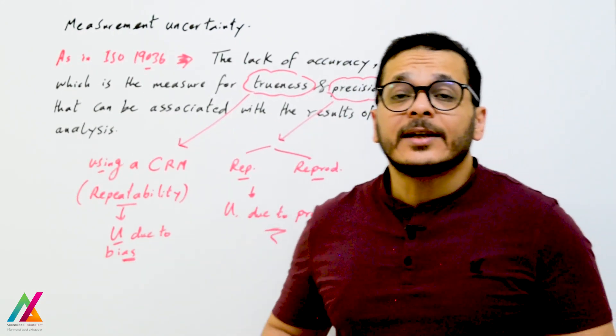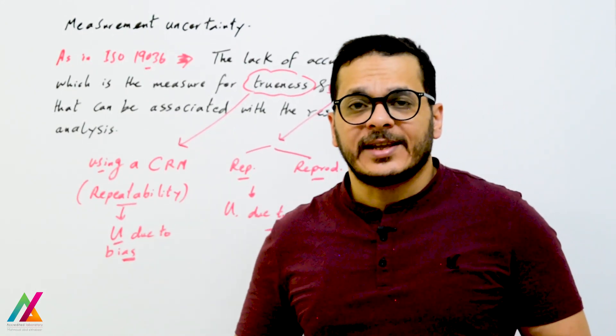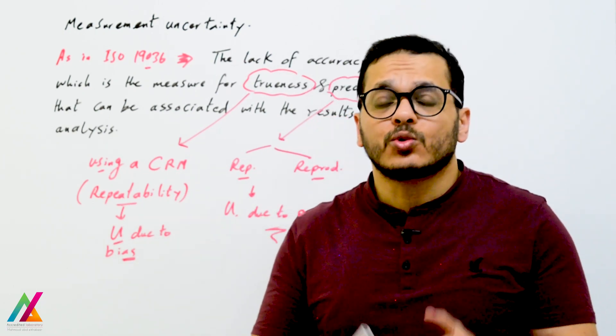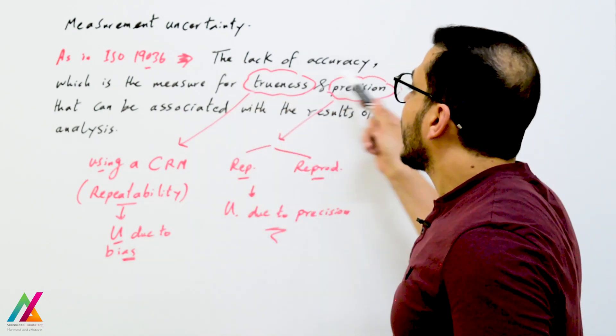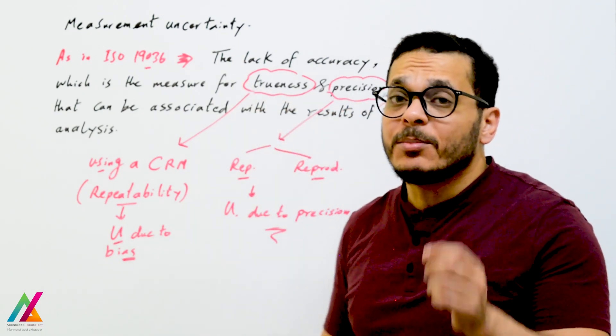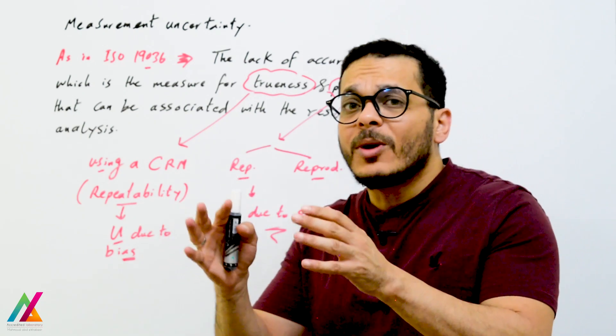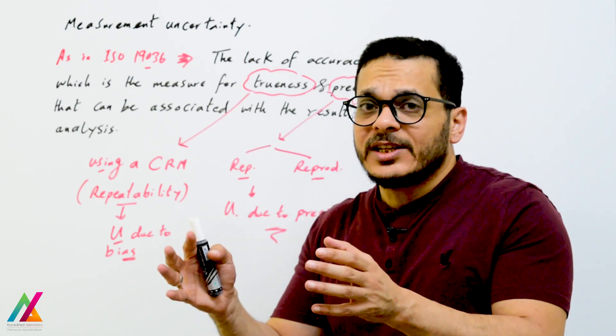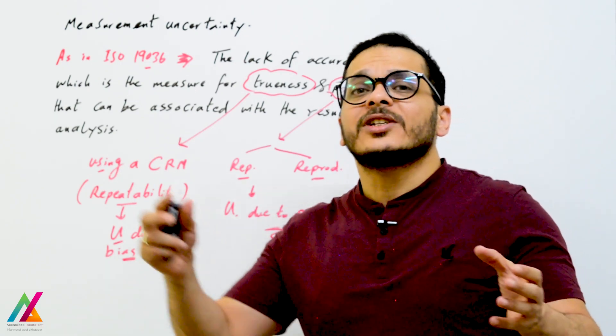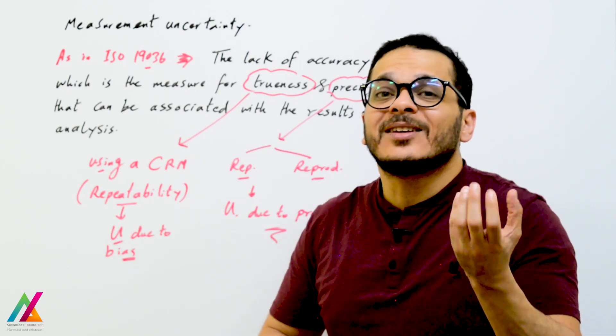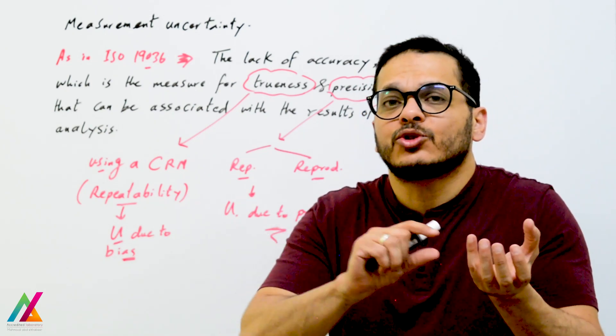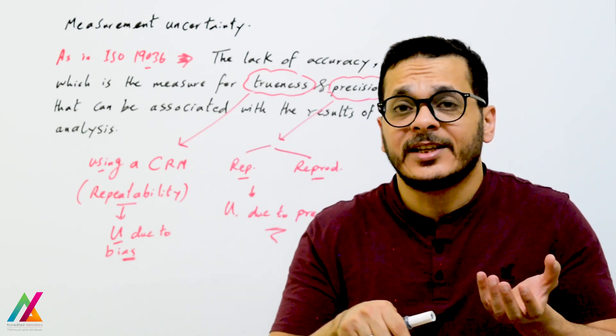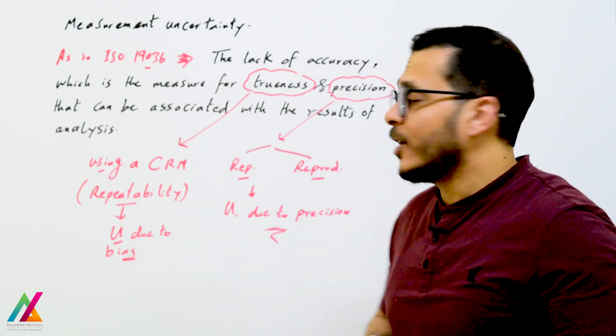As defined in ISO 19036 and other guidelines, measurement uncertainty accounts for the lack of accuracy — which is the measure of trueness — and the precision of the measurement. Accuracy reflects how close your measurement is to the true value. Trueness can be calculated using bias, which is the difference from the true value. For microbiology, you don't have a true value, but for chemical analysis it can be calculated.